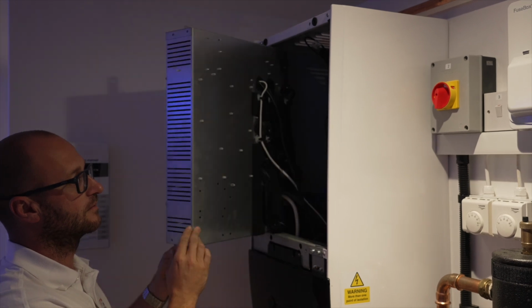Before considering mounting the unit, please be mindful of clearances that the Hydrobox requires. It must be mounted a minimum of 1,150 millimeters from the floor to the bottom of the unit and have a clear 200 millimeters minimum above the unit. The other thing you will need to consider is that once the front panel is removed, the inner electrical section hinges out like a cupboard door and will require 500 millimeters of clear space in front to allow this to happen.